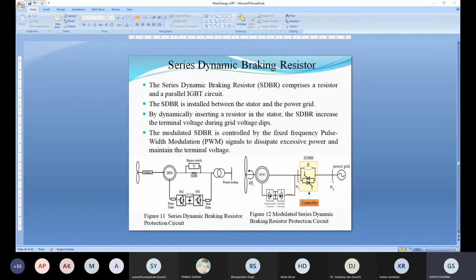First is the series dynamic braking resistor. It is connected with the stator, because we are looking at stator side techniques. So here the series dynamic braking resistor is connected between the stator and the grid. When there is normal operation, this bypass switch is closed and this resistor will not come into the picture. Under abnormal condition or fault, this bypass switch will open, and this SDBR, series dynamic braking resistor, will come into the picture. That will be connected between the stator and the grid.